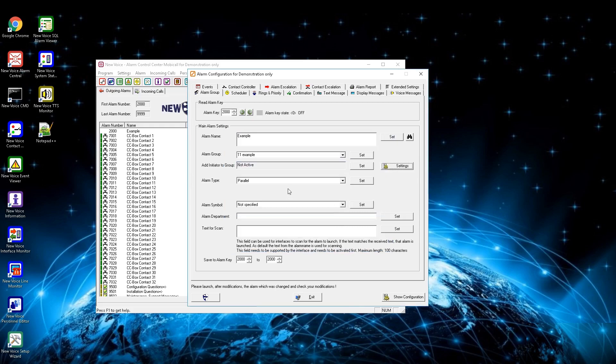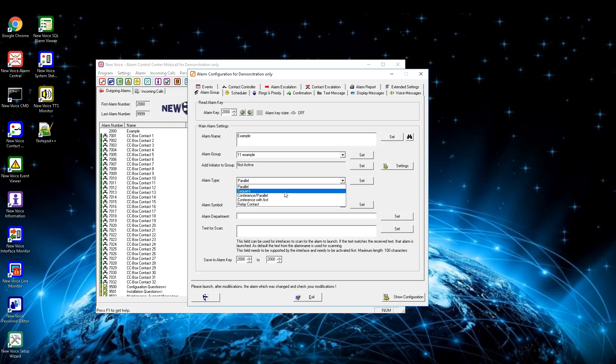The option alarm type defines how the alarm is processed. You can define between parallel, where MobiCall tries to reach all entries at once, and sequence, for calling every person in a row. If one entry picks up the call the other calls won't be processed.